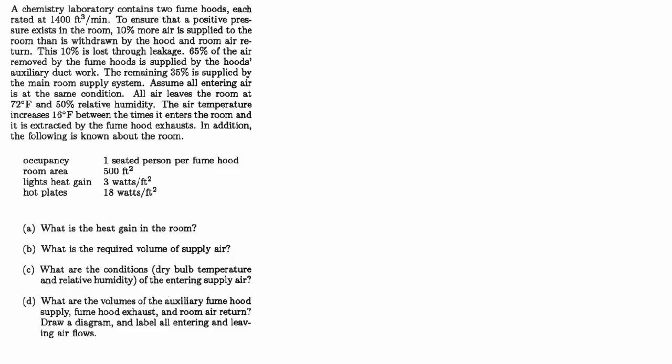In addition, the following is known about the room: occupancy is 1 person per fume hood, room area is 500 square feet, lights heat gain is 3 watts per square foot, and hot plates are 18 watts per square foot.